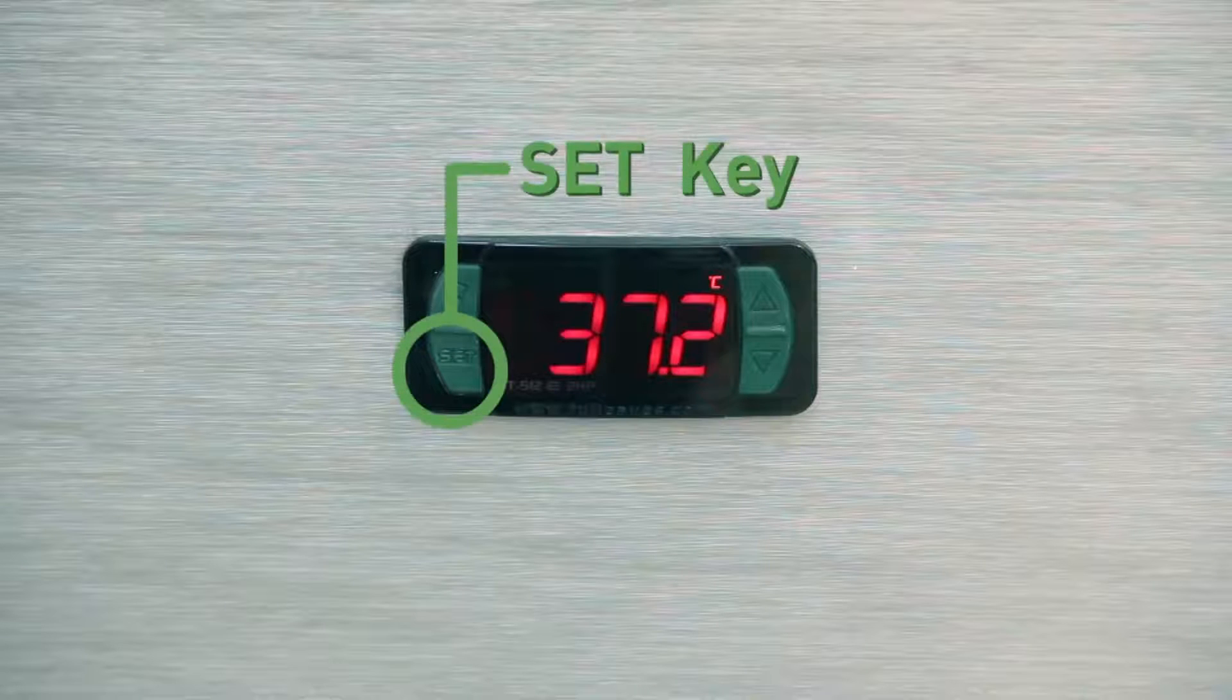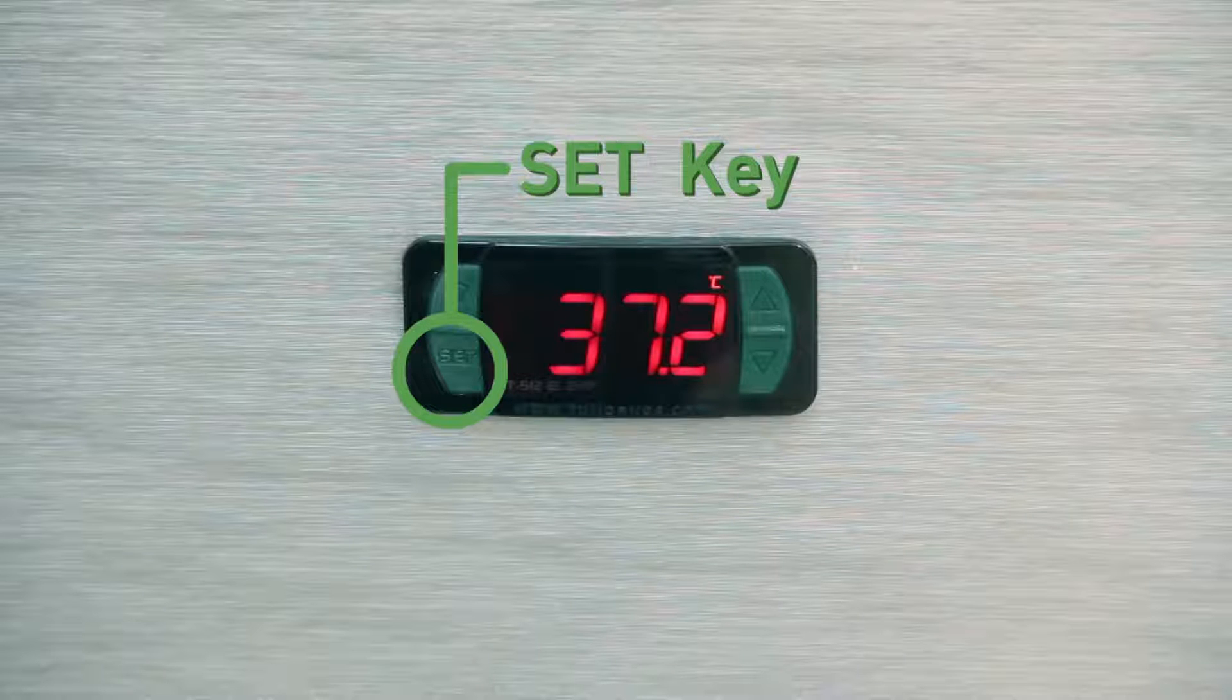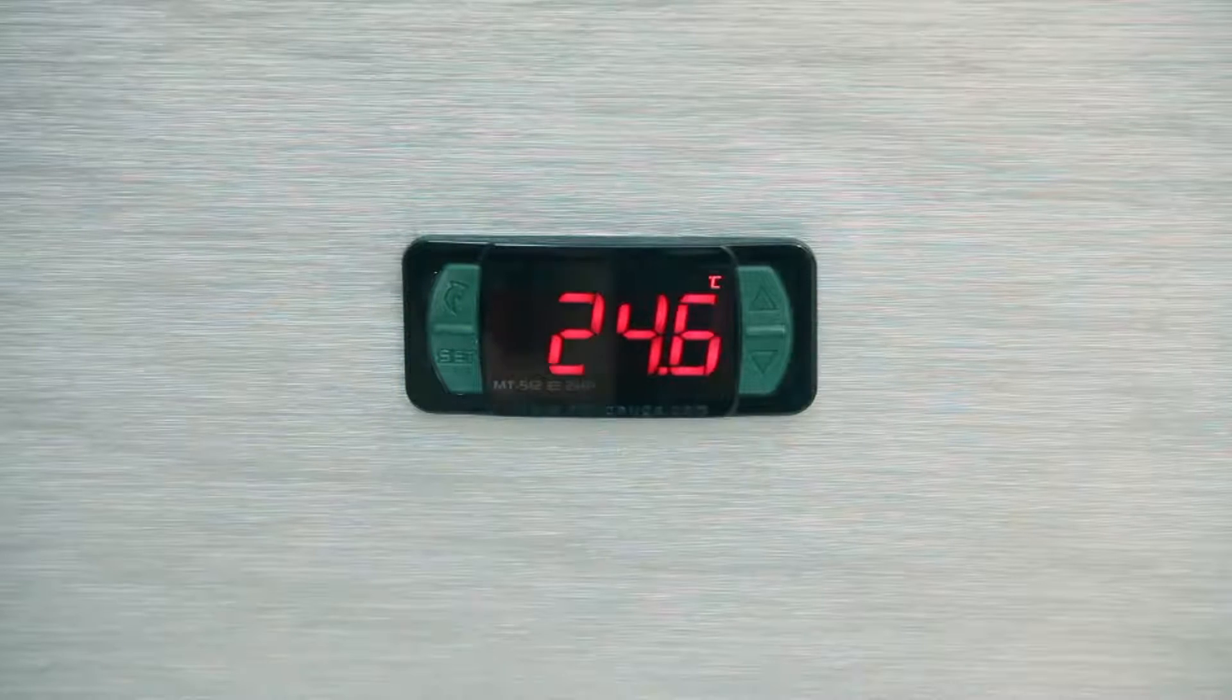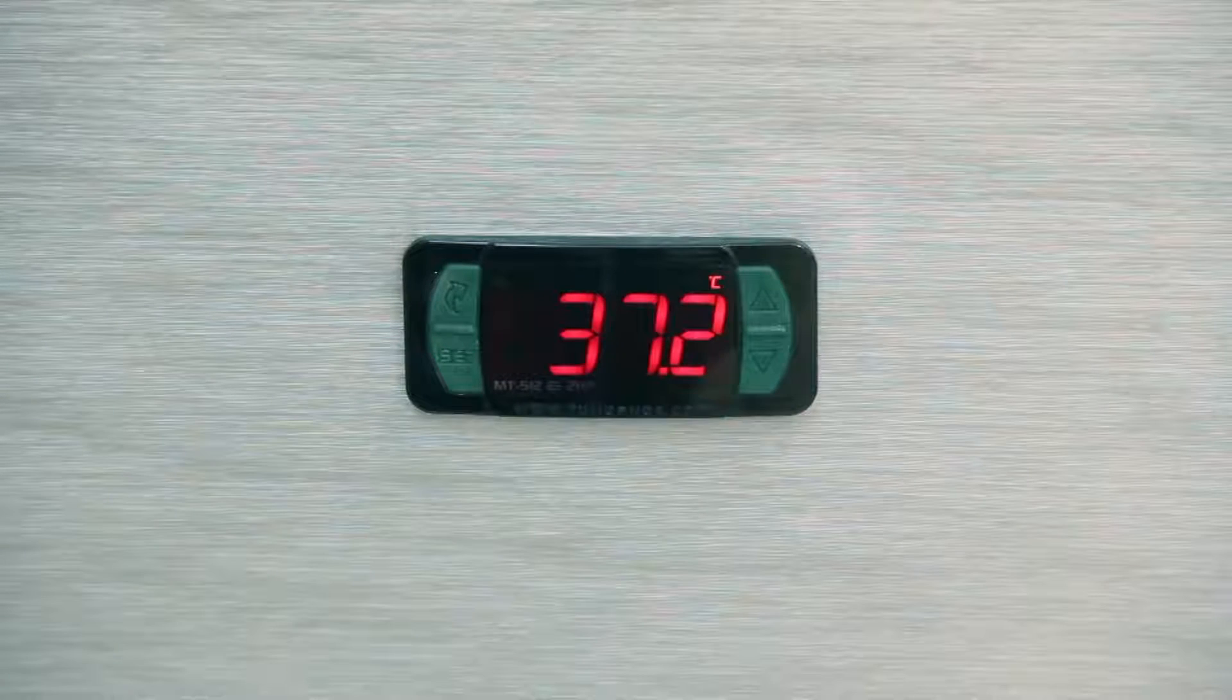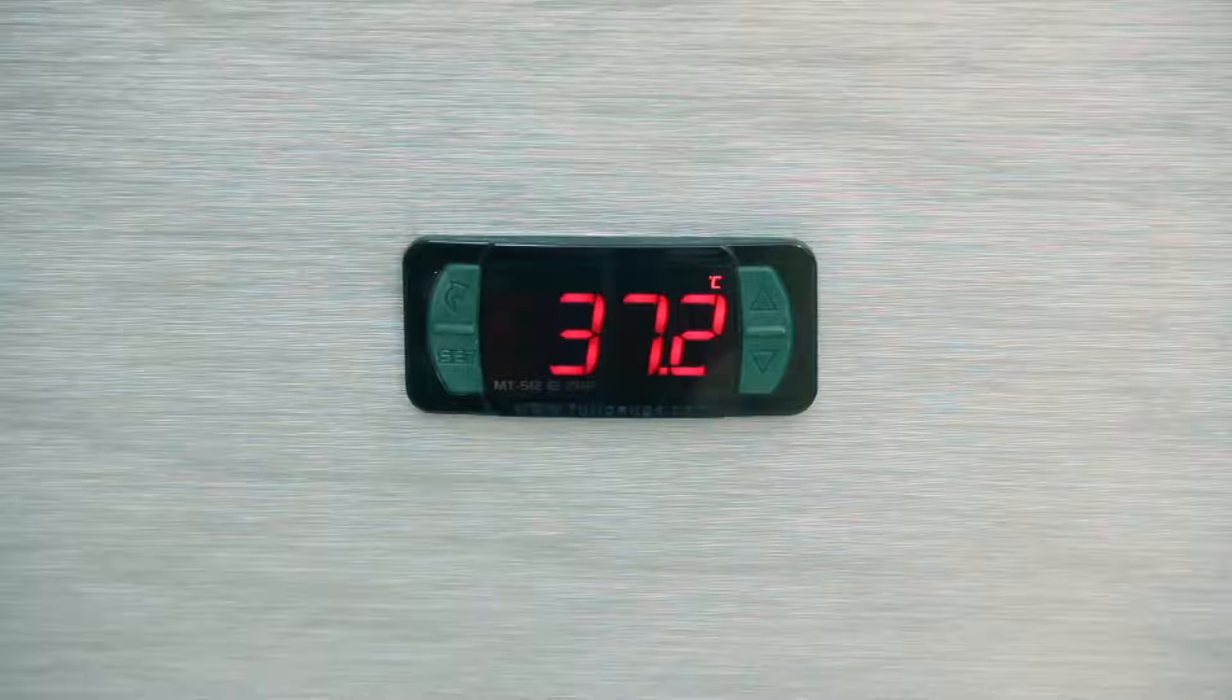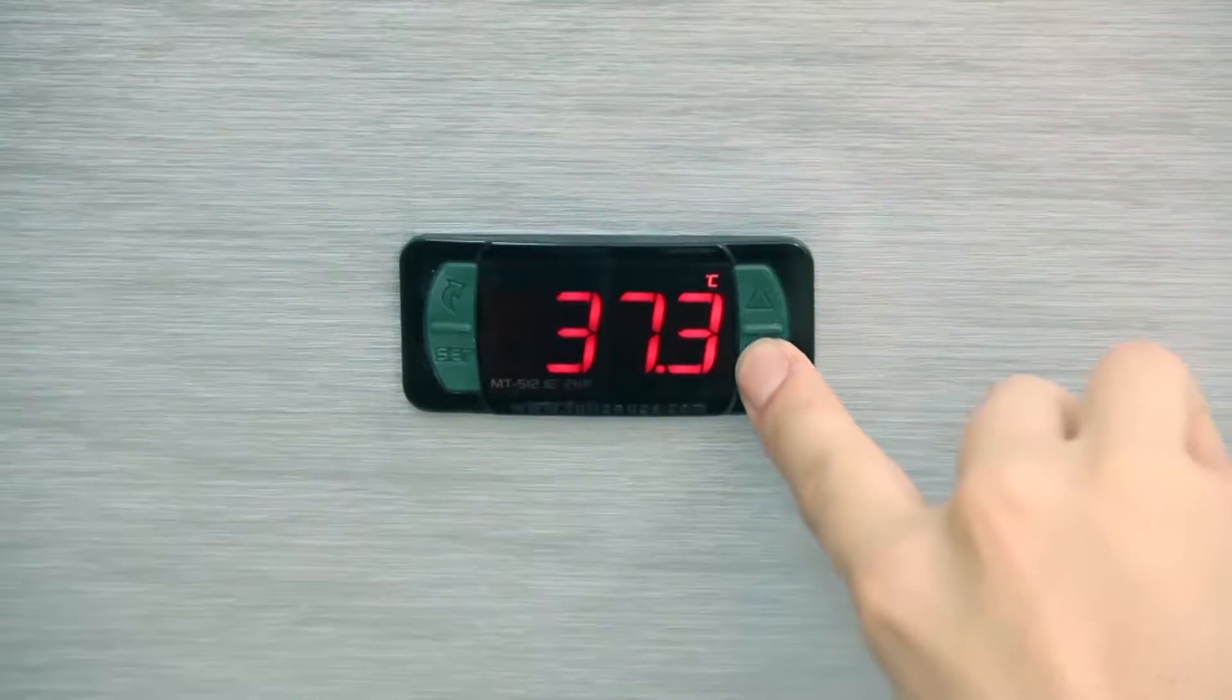Basic operations. Set point. The set point is the function we set to switch off the installation charge. The set key allows access to this function and also meets the confirmation function or enter for all controller settings. To change the set point, press set for 2 seconds until the set message appears on the display. When the key is released, the adjusted control temperature will be shown. Use the up or down keys to change the value. When you get the temperature value, press set to record it.